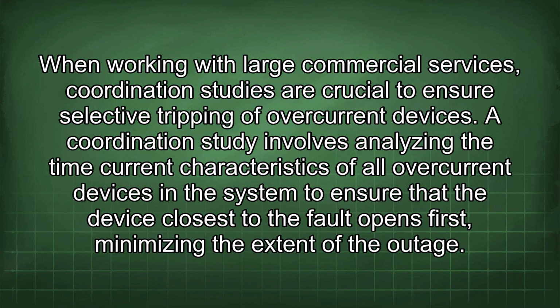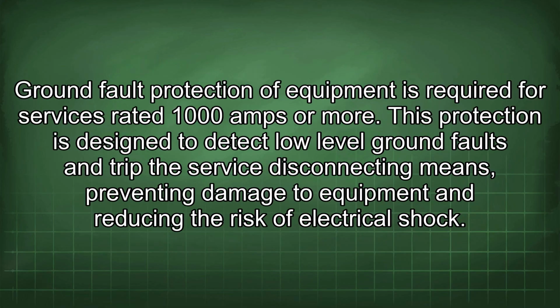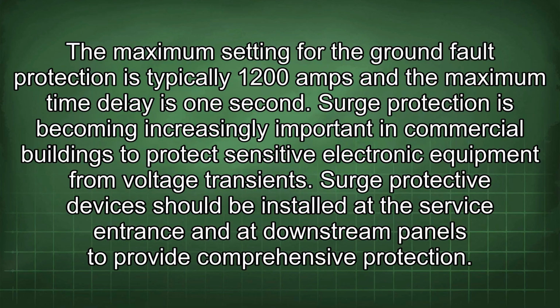When working with large commercial services, coordination studies are crucial to ensure selective tripping of overcurrent devices. A coordination study involves analyzing the time current characteristics of all overcurrent devices in the system to ensure that the device closest to the fault opens first, minimizing the extent of the outage. Ground fault protection of equipment is required for services rated 1000 amps or more. This protection is designed to detect low-level ground faults and trip the service disconnecting means, preventing damage to equipment and reducing the risk of electrical shock. The maximum setting for the ground fault protection is typically 1200 amps and the maximum time delay is 1 second.